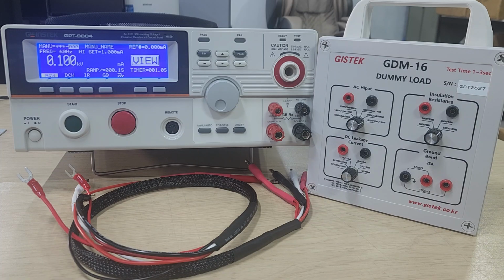In general, an electrical safety standard tester is a tester that checks whether the produced device under test meets or passes the normal electrical safety standard. The dummy load is a facility to check whether the electrical safety standard tester operates normally or performs normal inspection. Therefore, if high voltage and high current are applied to the dummy load for 60 to 120 seconds while the electrical safety standard tester inspects the dummy load, it will be damaged.